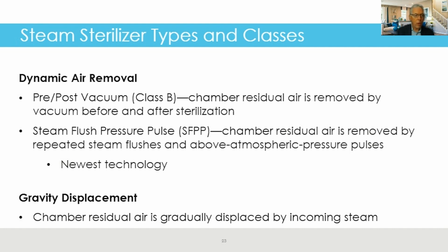Now, we talk here about steam flush pressure pulse. In the chamber, the residual air is removed by repeated steam flushes. There are above atmospheric pressure pulses - that's how the steam is pushed out. I will tell you that gravity displacement is slower because the air in the chamber is actually displaced just by the incoming steam. That's why - am I right, Lisa? These dynamic air removal machines are probably almost 30% faster, aren't they?